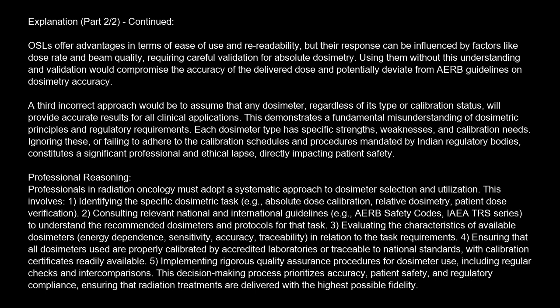guidelines on dosimetry accuracy. A third incorrect approach would be to assume that any dosimeter, regardless of its type or calibration status, will provide accurate results for all clinical applications. This demonstrates a fundamental misunderstanding of dosimetric principles and regulatory requirements. Each dosimeter type has specific strengths, weaknesses, and calibration needs. Ignoring these, or failing to adhere to the calibration schedules and procedures mandated by Indian regulatory bodies, constitutes a significant professional and ethical lapse, directly impacting patient safety.